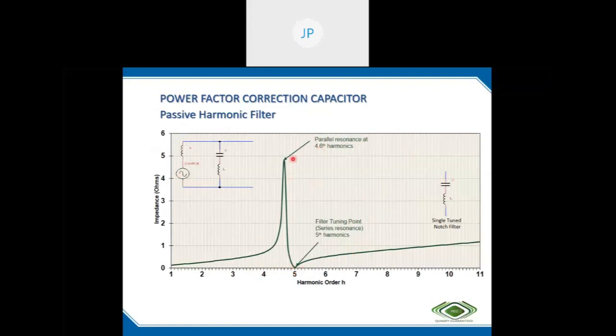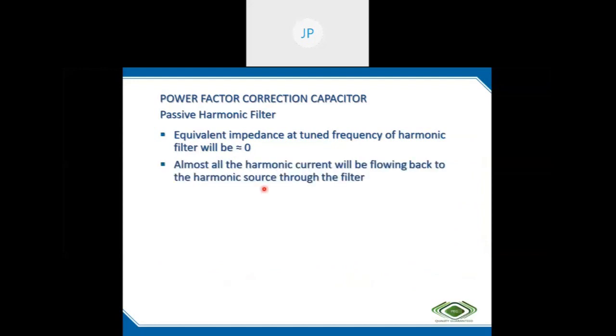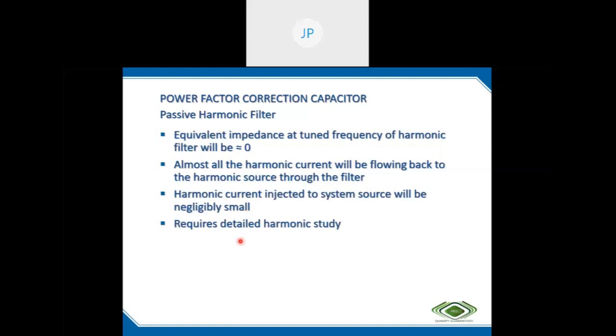Here also there is a resonating point, but there is no harm because there are no harmonics there. We have to cross check it. This should not come at the third harmonic point. If the resonating point is shifted somewhere here, whatever third harmonic is available will be amplified. So we have to cross check the design and take corrective measures. Impedance at the tuned frequency is zero. Almost all harmonic current will flow back to the harmonic source through the filter. The harmonic current injected will be negligibly small. The only requirement is a detailed harmonic study. It's an economically justified solution for harmonic mitigation.